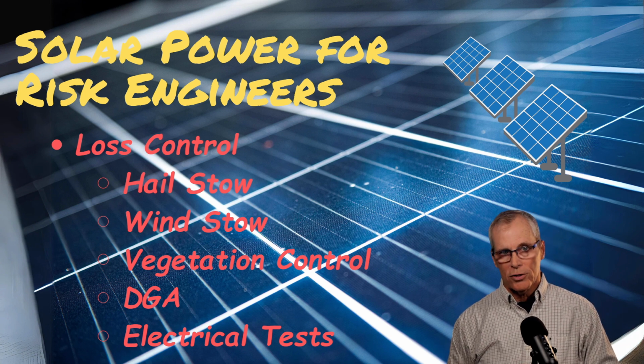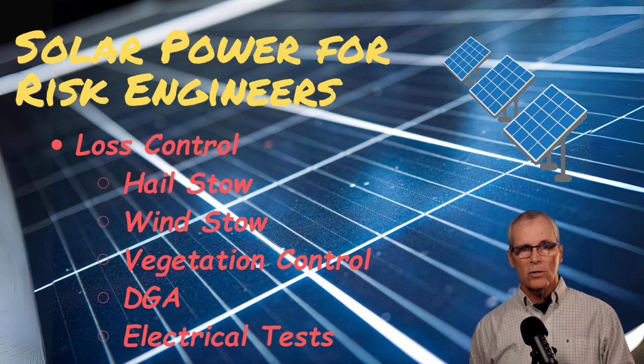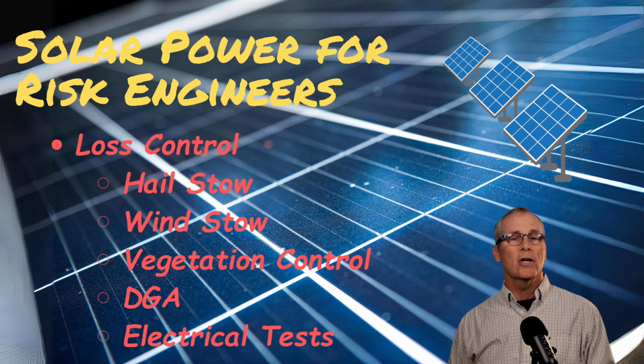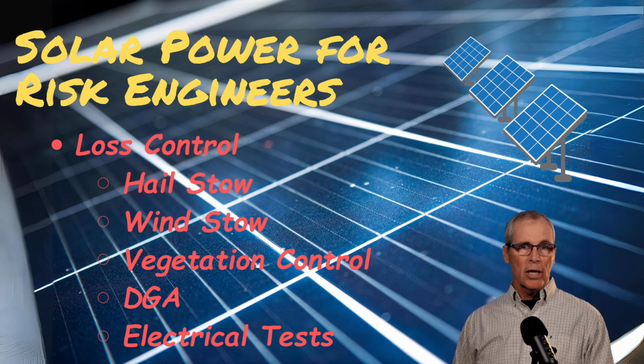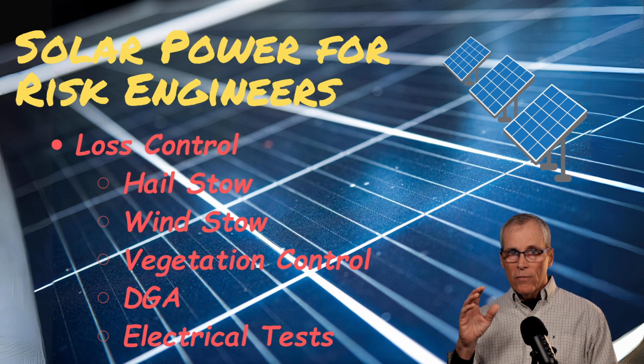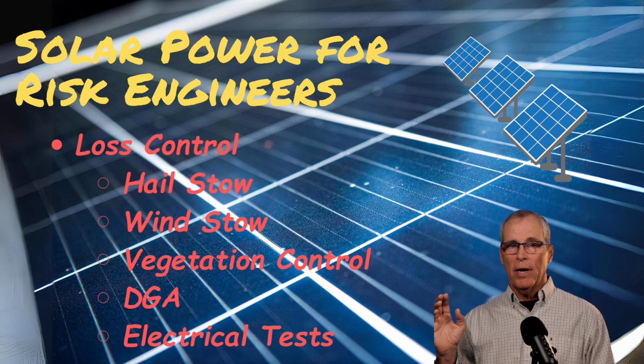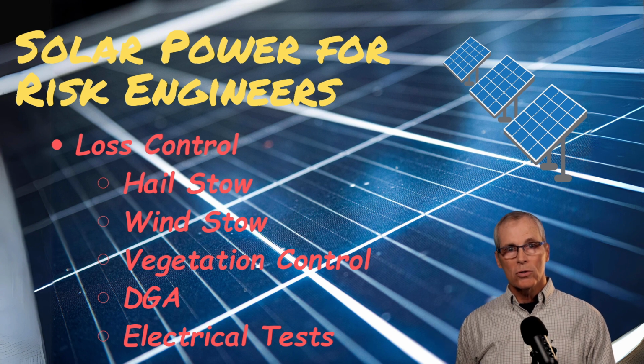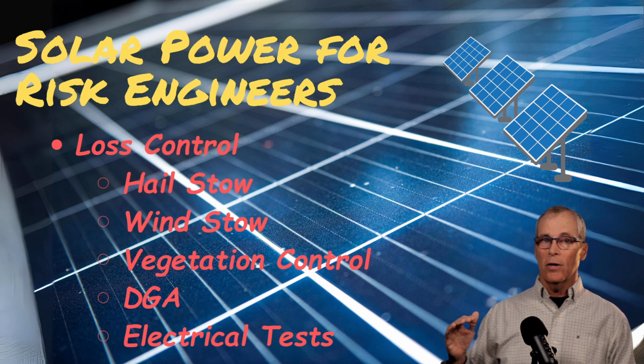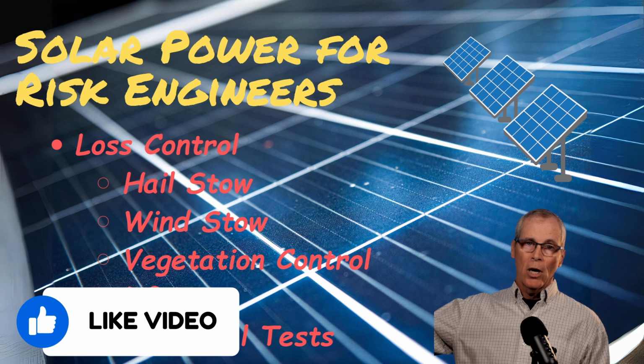And then electrical tests. We'll talk about dissolved gas analysis and electrical tests. They're going to be for your transformers, your inverters, your combiners, all your electrical equipment. You're going to want to infrared scan that equipment and make sure that it's not overheating and that you don't have any loose connections. And when I say infrared, don't fall into the trap that a lot of solar operators think that means a drone flying and scanning all your panels.